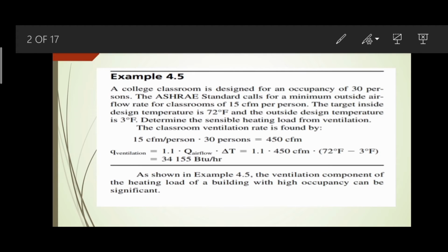So, ano nga ba muna ang ASHRAE? ASHRAE is the American Society of Heating, Refrigerating, and Air-Conditioning Engineers. So, the target inside design temperature is 72 degrees Fahrenheit and the outside design temperature is 3 degrees Fahrenheit. So, ang hahanapin natin is the sensible heating load from ventilation. So, para makuha natin yung ventilation rate, kailangan natin pag-timesin yung CFM per person times the total persons, which is 450 CFM. Para naman makuha natin yung Q ventilation, kailangan nating pag-timesin yung 1.1, the airflow, and the CFM na total na nakuha natin kanina, which is 450.